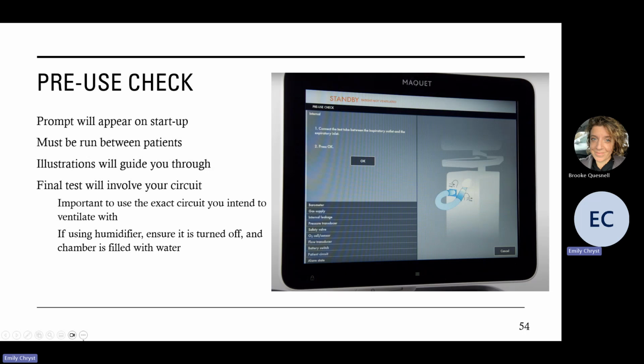This can be a separate test, or it can be part of your pre-use check. So we can test patient circuits whenever we change a circuit without having to go through this whole pre-use check. But it's going to be a part of the initial test. That being said, it's really important to use the exact circuit you intend to use on the patient when you're doing this circuit check. And if you're using a humidifier, make sure that the humidifier is turned off and you have the chamber filled with water.